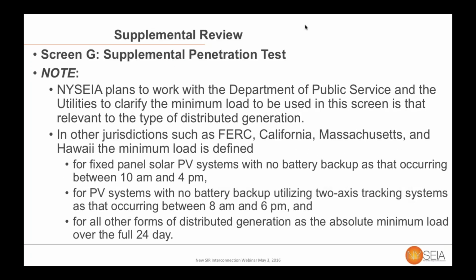So the only question mark that we have on this is that in most other jurisdictions that use this type of screen, for instance California and Massachusetts, they use different time windows for the minimum load for solar and other types of distributed generation. For solar, they look at what's called the daytime minimum load, from 10 to 4. For two-axis tracking systems, they look at 8 to 6. And then for all others, which can operate at night or any time of the day and year, they look at the full 24-hour minimum load. Clarifying exactly what time window this will be calculated over can have an important effect.